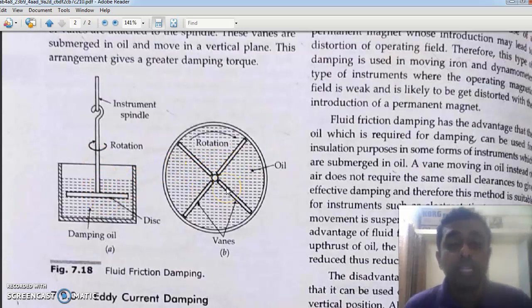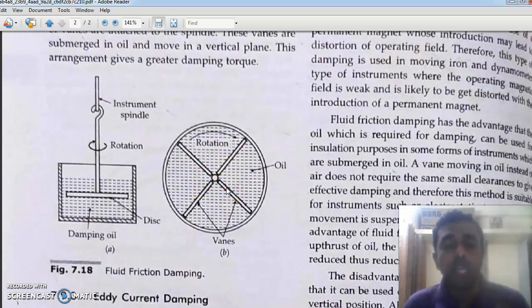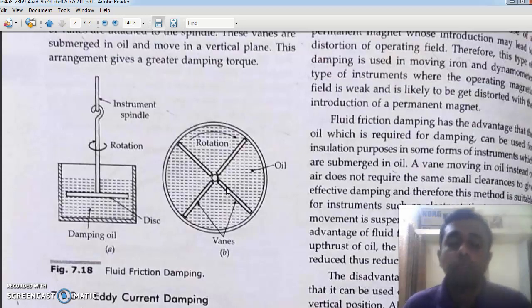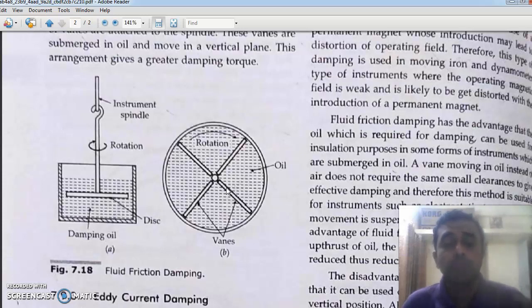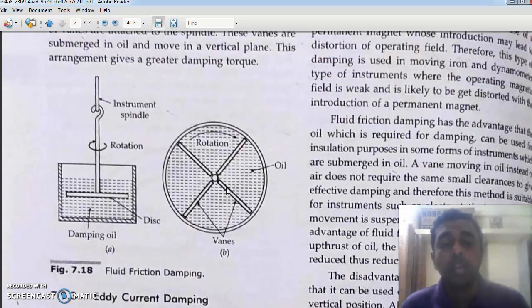The vanes will be rotating inside oil. Oil has some viscosity, and viscosity is actually friction for the liquid. So this frictional force will be opposing the motion of the vanes. The oscillations or the swings about the equilibrium or steady state point are nullified by the viscosity of the oil.